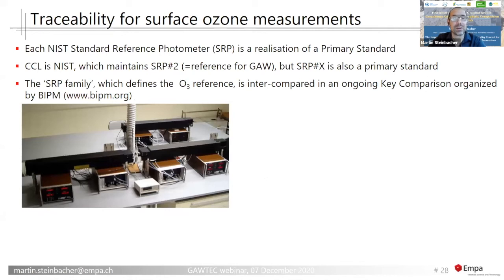CO2 was again rather an easy case when we look at other gases like ozone. Ozone is a very reactive gas, as I mentioned before. It cannot be stored in high pressure cylinders because it will vanish immediately. For ozone, it's different. There, the reference is not a suite of calibration tanks like we had at NOAA, but standard reference photometers, all built by the National Institute of Standards and Technology in the US. And there are about 60 of these out there, and they maintain the reference for GAW.